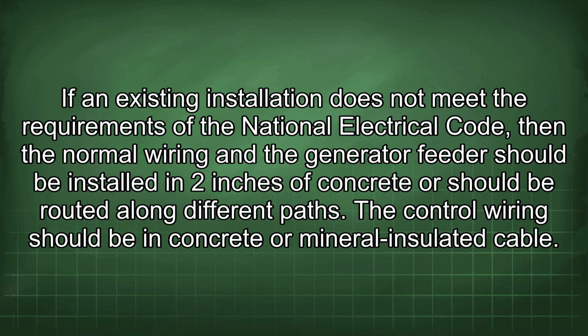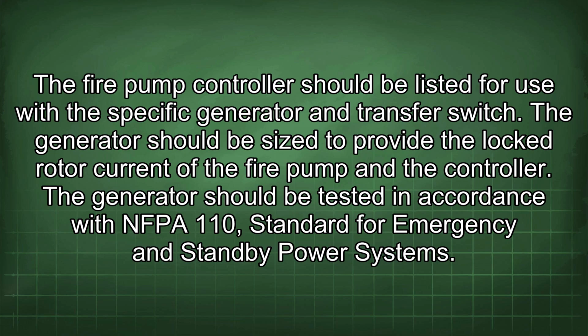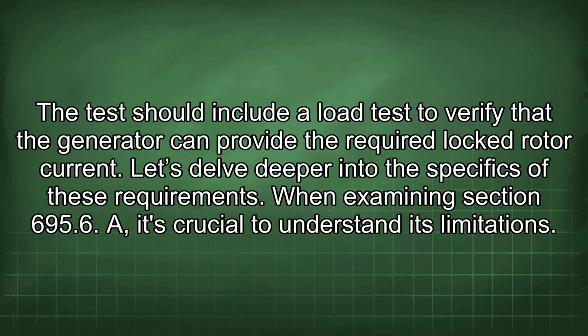If an existing installation does not meet the requirements of the National Electrical Code, then the normal wiring and the generator feeder should be installed in 2 inches of concrete or should be routed along different paths. The control wiring should be in concrete or mineral insulated cable. The fire pump controller should be listed for use with the specific generator and transfer switch. The generator should be sized to provide the locked rotor current of the fire pump and the controller. The generator should be tested in accordance with NFPA 110, standard for emergency and standby power systems. The test should include a load test to verify that the generator can provide the required locked rotor current.